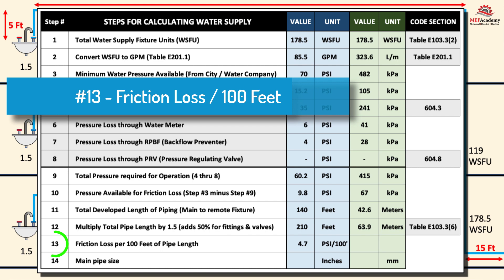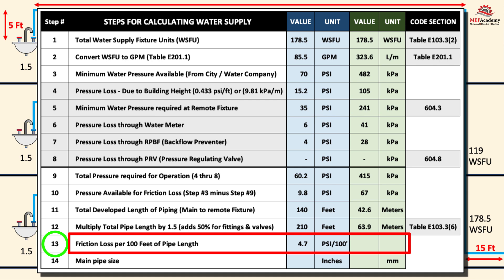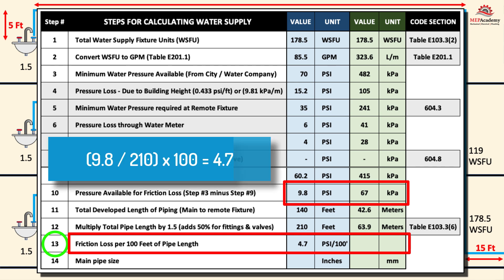Step 13: Determine the Friction Loss per 100 Feet. This calculation determines the leftover pressure that can be used to overcome friction loss in the pipes and fittings. From Step 10, there is 9.8 PSI or 67 kPa available for friction loss. The calculation is: 9.8 ÷ 210 feet × 100 = 4.7 PSI per 100 feet.